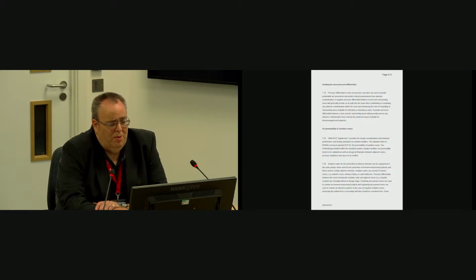What you are describing is a room that would be at neutral pressure, for want of a better term. It is neither positive nor negative to a surrounding or adjacent room. You will get minimum air transference through that arrangement, which are the fundamental principles of the PPVL style isolation room. The room is at neutral pressure to surrounding areas. The positive pressure is created in the lobby, and the negative in the ensuite or extracted from the room directly.